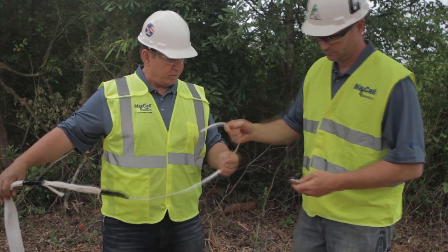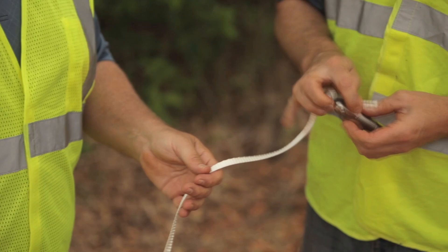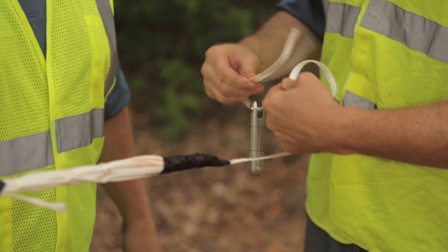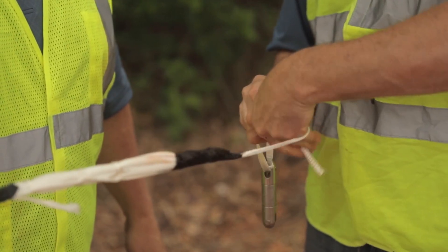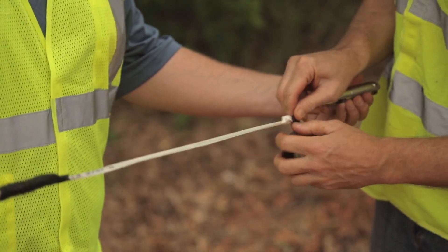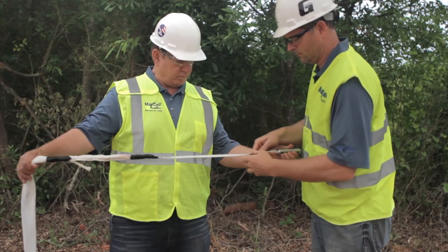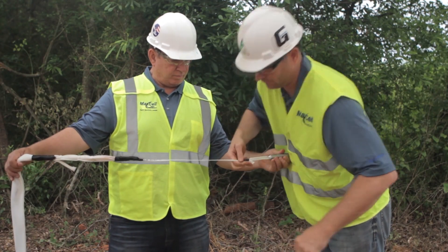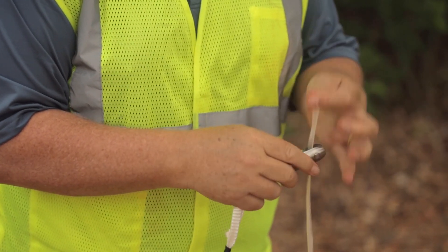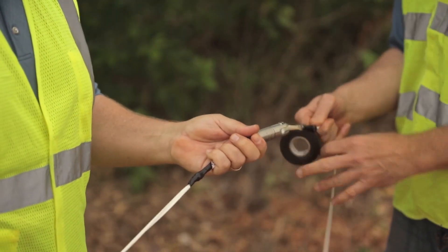The most important tool to make your MaxCell installation a success is a ball bearing swivel. A ball bearing swivel must always be used between the pull tape or rope and MaxCell — this keeps the MaxCell from twisting. Using a bowline knot, attach the existing pull tape from the rigid conduit to the other end of the swivel. Remember to tape all knots.